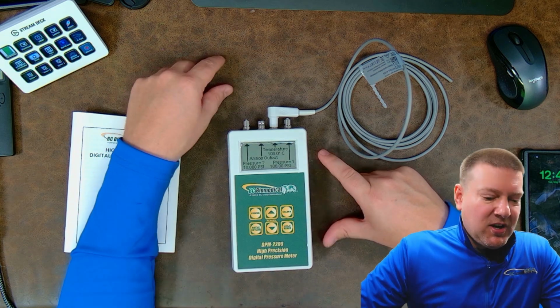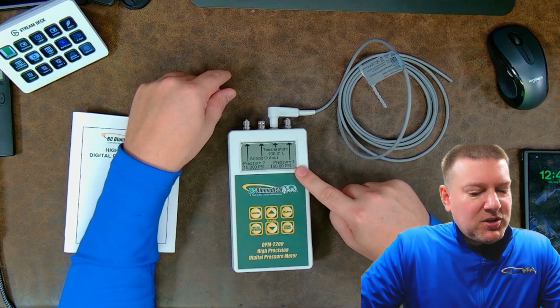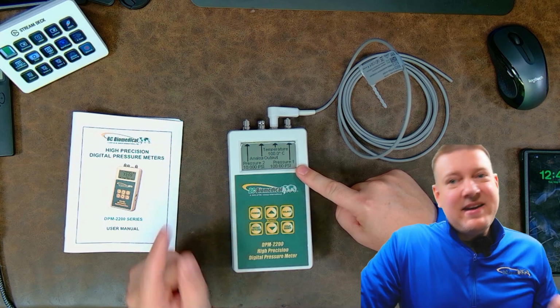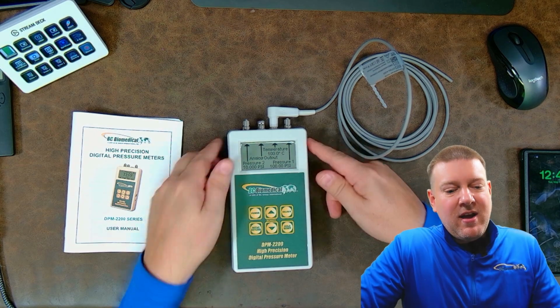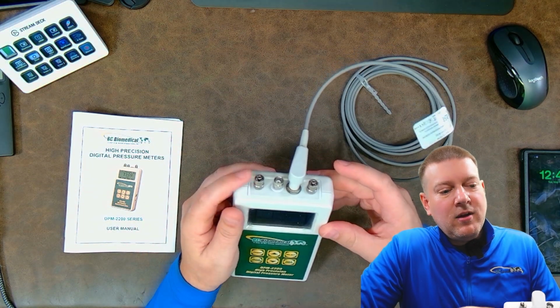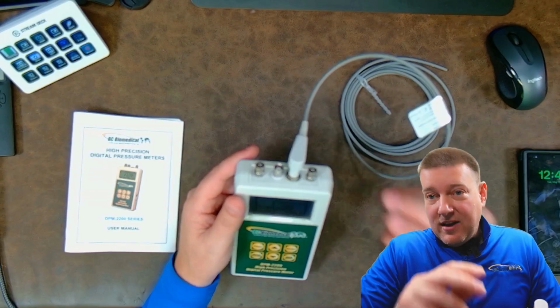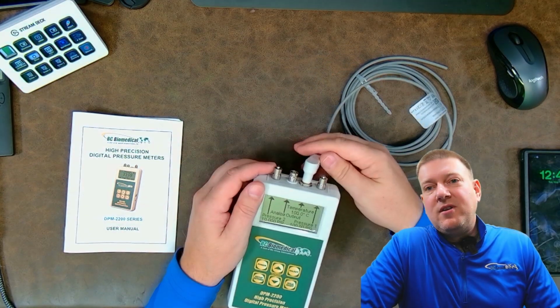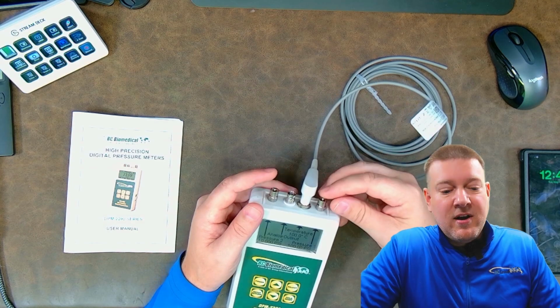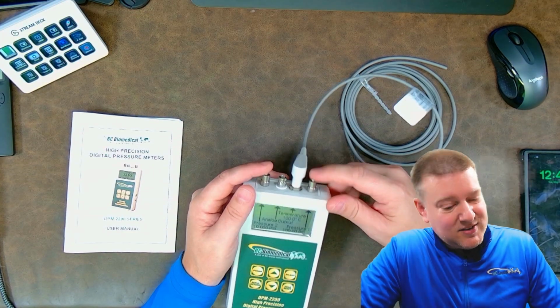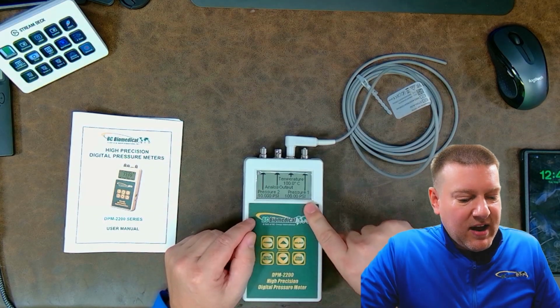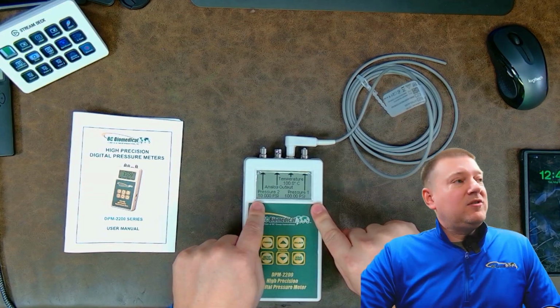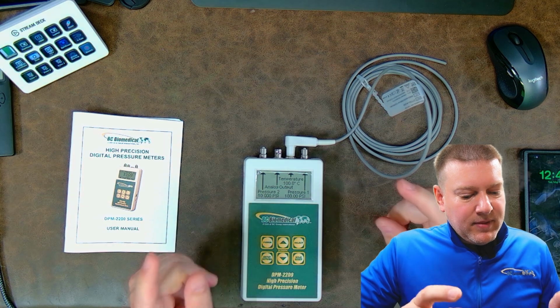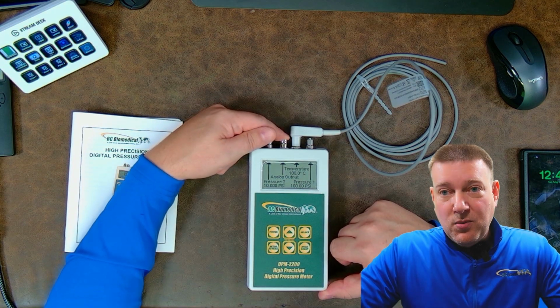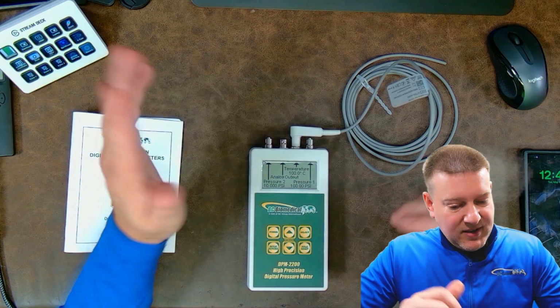Here is that flash screen that we started out with. Pressure transducer 1 goes up to 100 psi. That is line level pressure. And because these here are male luer locks, these ones here have locking pressure ports. So it's not just a barb where you push something on. Luer locks twist on and they lock on. So you can handle high pressures. This one does go up to 100 psi on pressure port 1. Pressure port 2 goes up to 10 psi. We have an analog output here, so if you want to chart out your analog data, that's up to you.